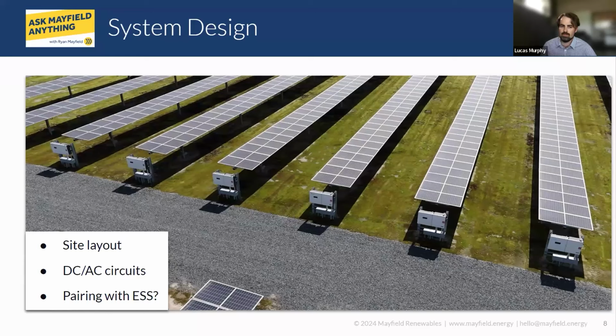A few years ago, it almost lined up perfectly with the advent of the 1500 volt DC string inverters that it made the most sense to design these as virtual central or cluster them at the main equipment pad, just because running DC at 1500 volts back to your pad was less expensive than running 480 or 600 volt AC throughout your system to a main equipment pad.